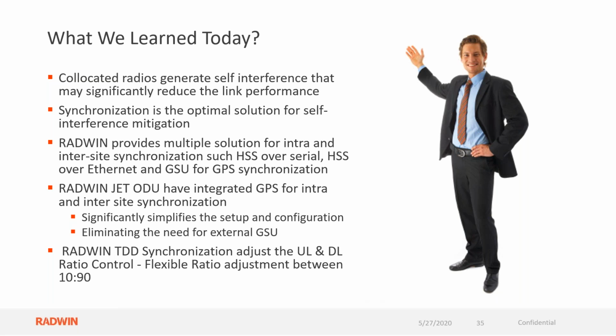So if the master or the GPS drops, the GSU unit, we have no backup. Of course, we can manually change one of the slaves to be the master, and this is a simple and easy solution. Just go to the configuration, change from slave to master, and you have a master. But it requires manual intervention to change the configuration. This is the answer for this.